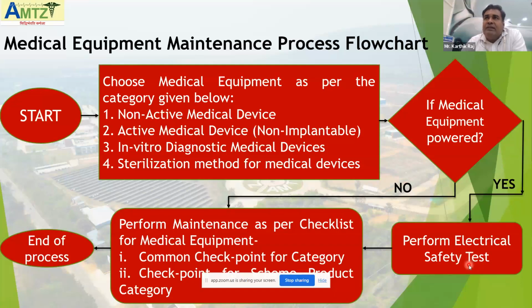Again, there are different standards in the market. That is the IEC 60601-1 standard, and then the IEC 62353 standard. Usually, once the equipment is installed in the hospital, we never go with the IEC 60601-1 standard, because that is used by the manufacturers.